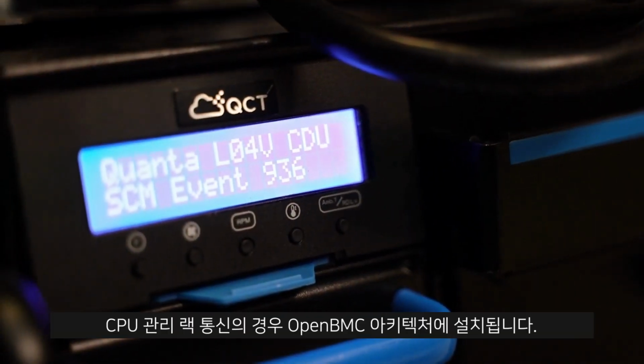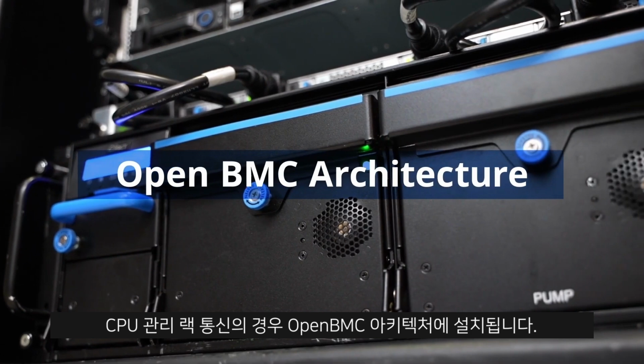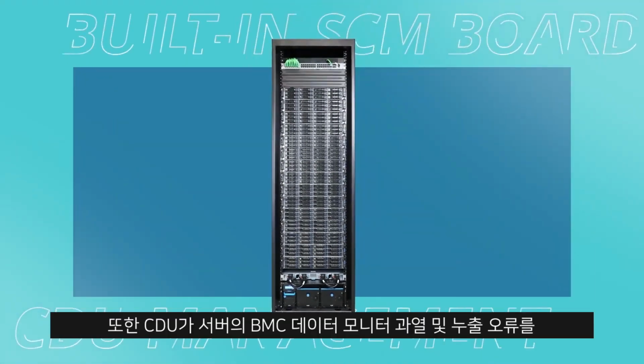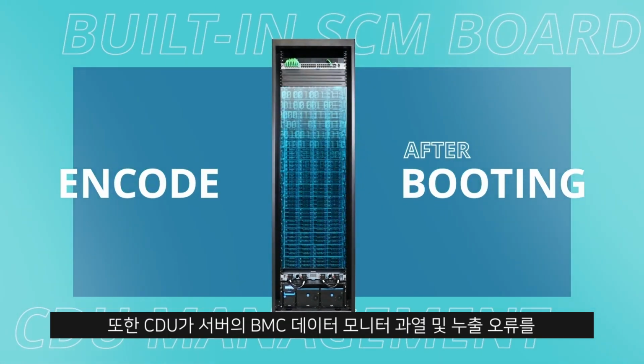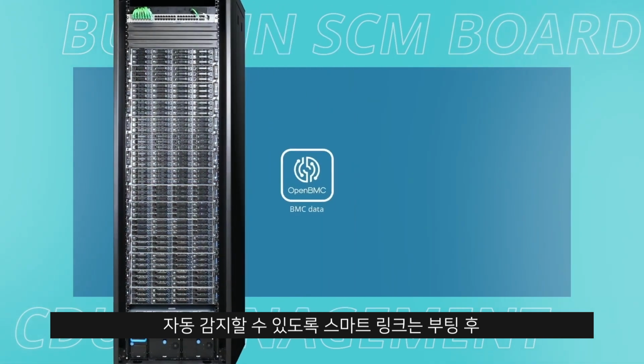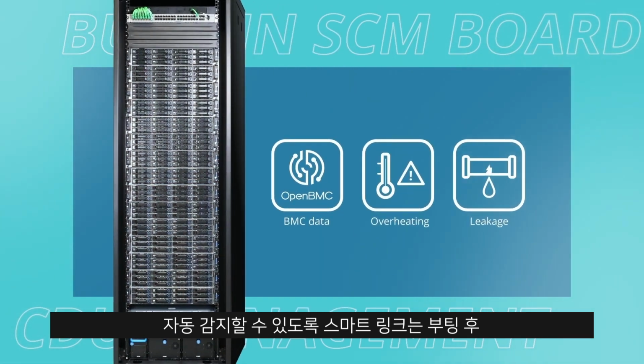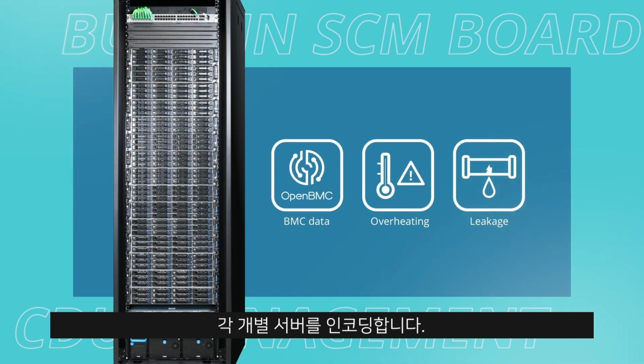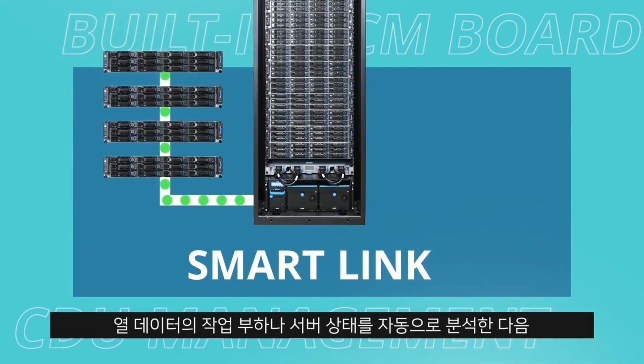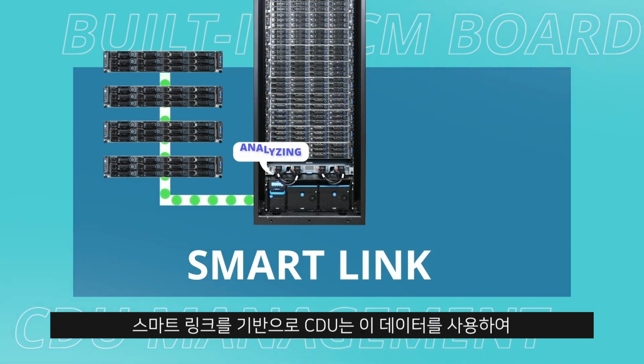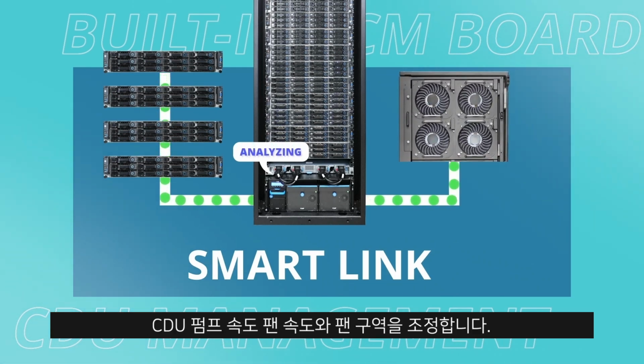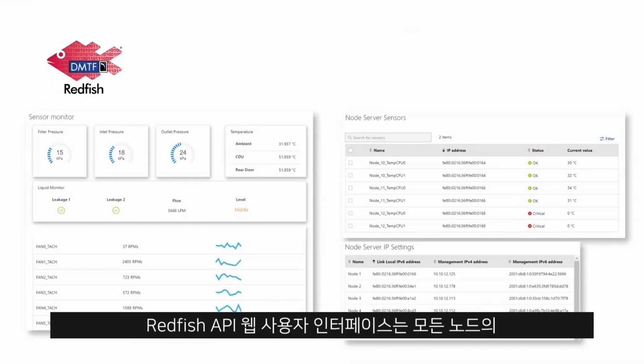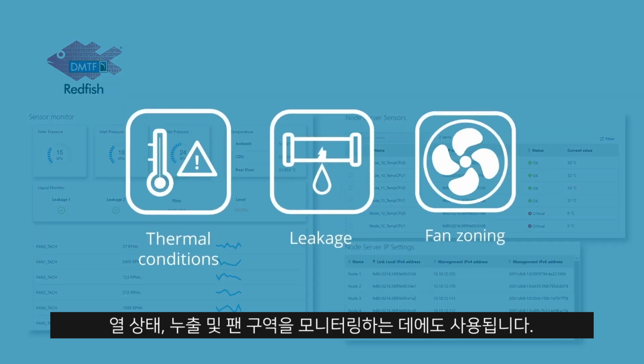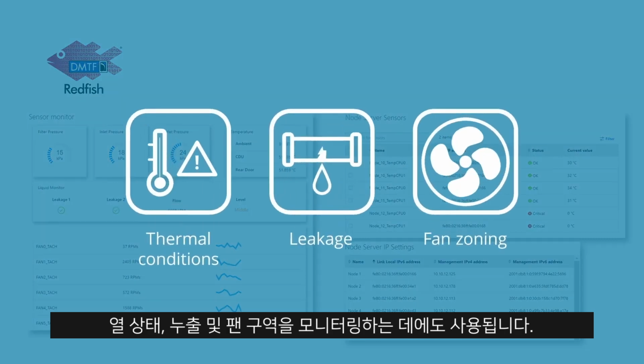For the CDU's management, rack communication is installed under an open BMC architecture. Additionally, a smart link encodes each individual server after booting, in order for the CDU to auto-detect the server's BMC data and monitor overheating and leakage errors. Based on this smart link, the CDU would use this data to automatically analyze workloads and thermal data or status of the servers to then adjust CDU pump speed, fan speeds, and fan zones. A Redfish API web user interface is also used to monitor thermal conditions, leakage, and fan zoning for every node.